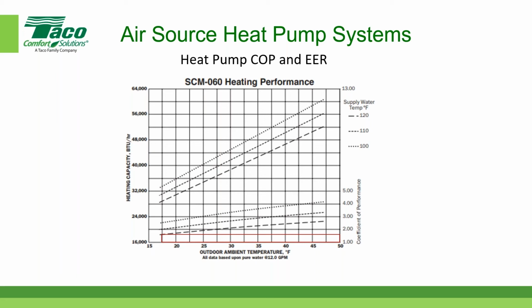Especially when you come in from the outside, like today, it's 22 degrees outside. And I come in the house, if the temperature inside is 70, I feel like I'm going to die because it's so hot. So I usually keep it around 67, 68 degrees. And so, with 68 degrees and 100 degree supply water temperature, you can easily heat a house if you have enough surface area in your terminal devices. So it's all about design. Yep. Okay, what are we going to talk about next?